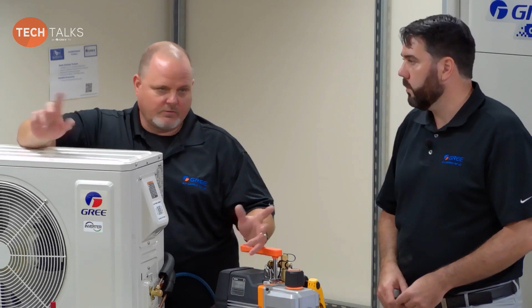Even though you powered it up, it doesn't mean you have to turn it on. You can have all your remotes in the off mode. All we want is power applied to this condenser while we're doing this whole evacuation process. And if you're around 50 degrees or higher, you probably only have to have power to it maybe a couple hours. Probably not even that long, maybe an hour.